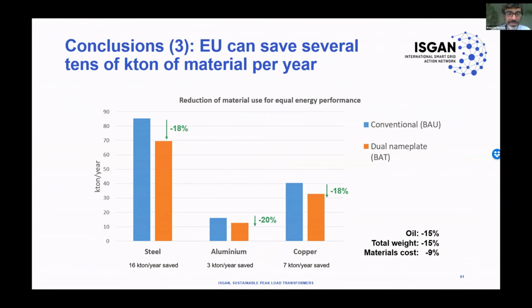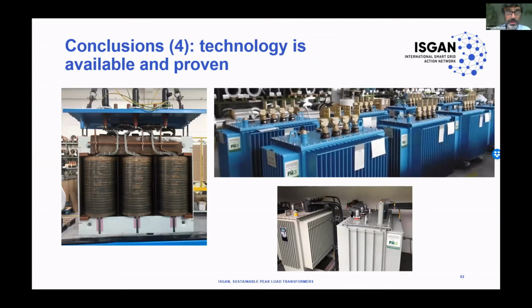And then, as said, the material savings are substantial, and this has been shown by a modeling exercise for the EU. If all replacements of distribution transformers would from now on go to a sustainable peak load transformer, we would save 16 kilotons of steel per year, 3 kilotons of aluminium, and 7 kilotons of copper. We would also save oil, and there would be a 9% reduction in material costs. And all this with a proven technology, which is available on the market and which has been tested in many cases, both in Europe and in the US and in South America. So the technology is there to be used. Thank you. That was it for today.